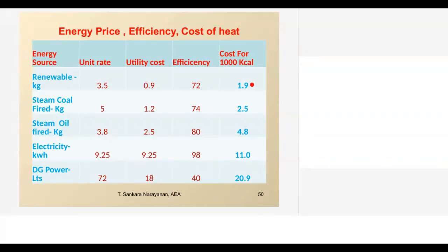But the agro-based and coal options can become neck to neck when the cost of agro waste changes, because instead of 3.5 rupees it is going to 5 rupees. This cost will change. This is the design efficiency of the agro-based system. If the operating efficiency is only 60%, then it may not be attractive. So whenever you are going for fuel substitution, it has to be compared with the efficiency of the system and the cost of heat. Because sometimes after 1 year or 2 years, what we have shown as reducing the cost may not reduce, it may increase the cost. So the cost of heat has to be reviewed whenever there is a change in the unit price. Electricity is again a high cost, diesel is again a luxury.